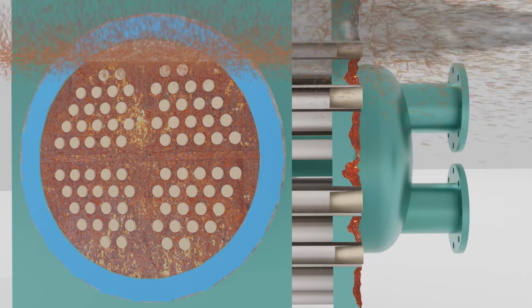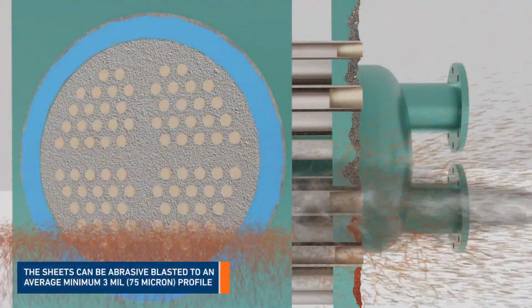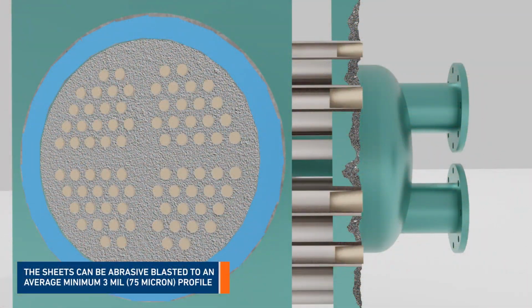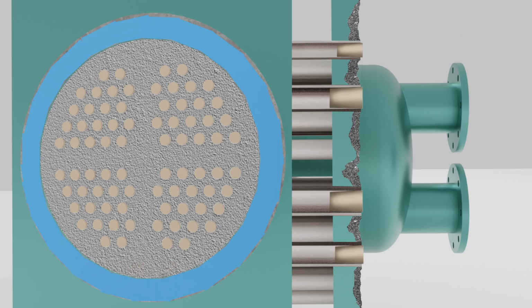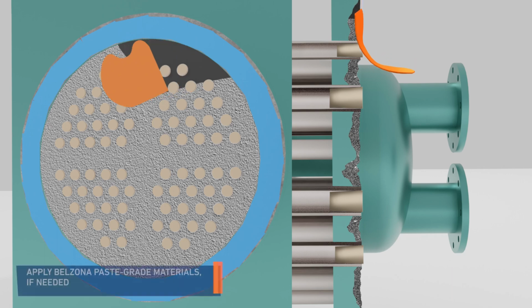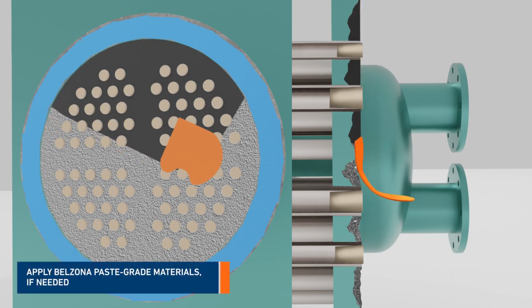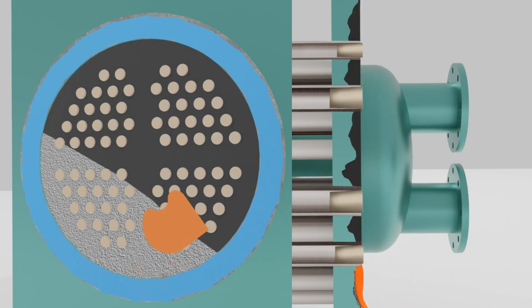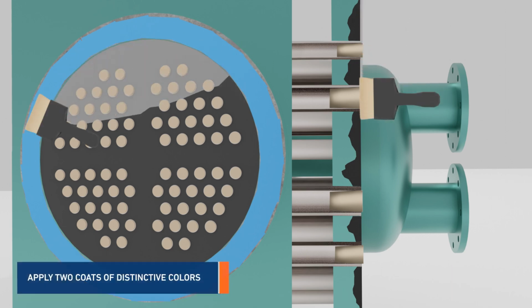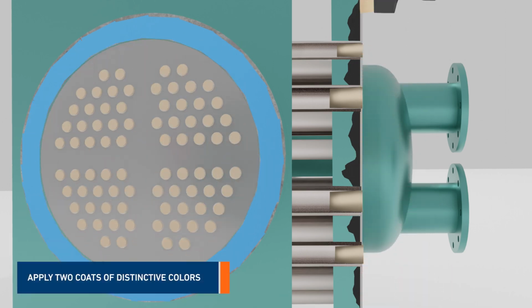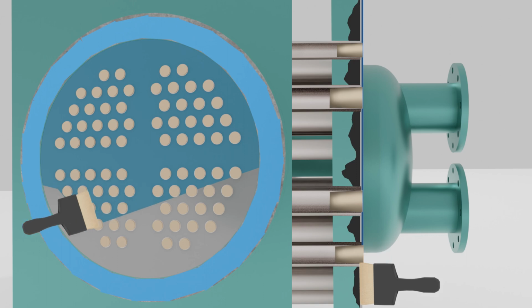Now that the tubes are protected, the sheets can be abrasive blasted to an average minimum of a 75 micron profile. If rebuilding of the tube sheet is needed, Belzona 100% solids epoxy-based paste-grade materials are applied using an applicator. Two coats of distinctive colors are applied until the minimum total thickness required is achieved.